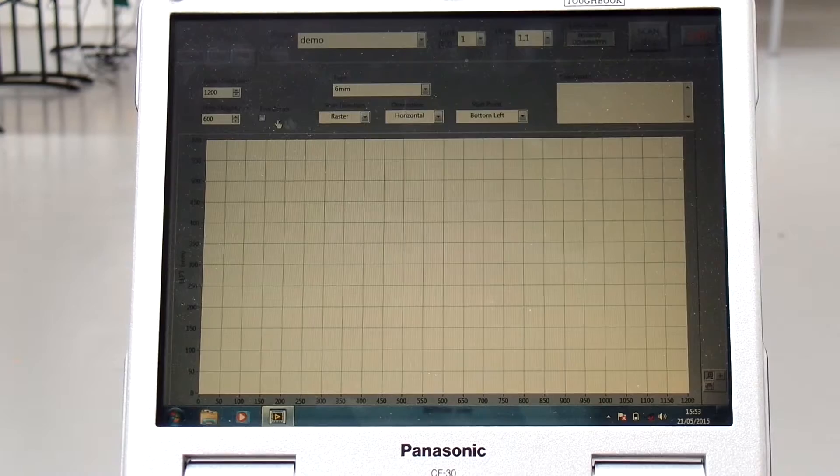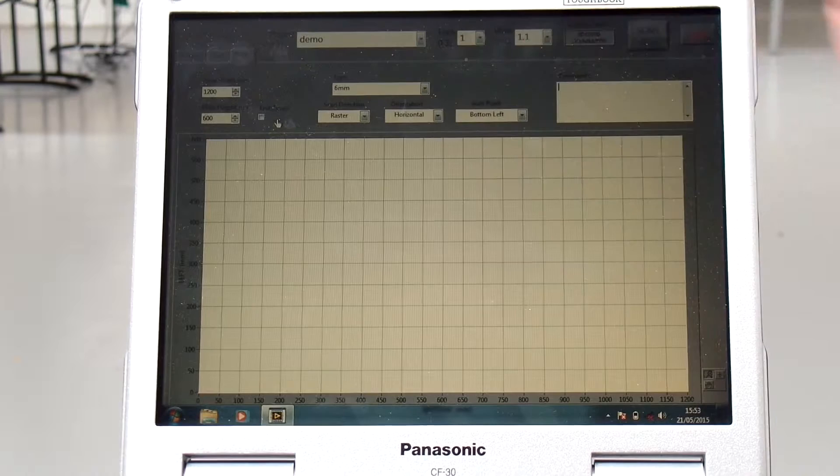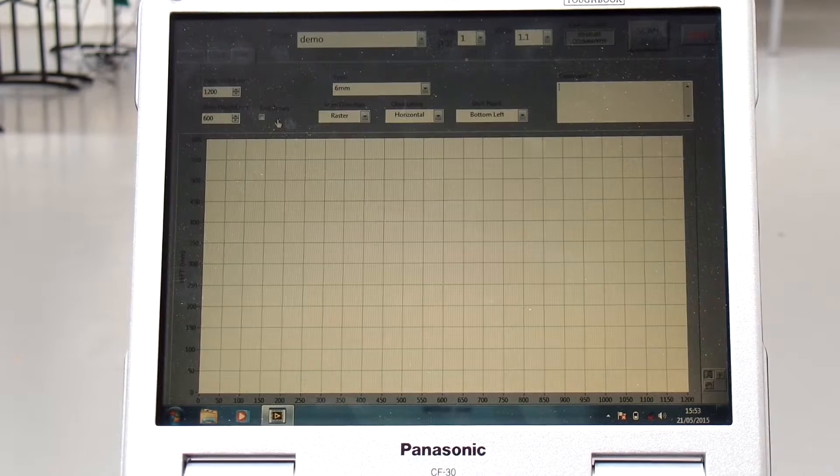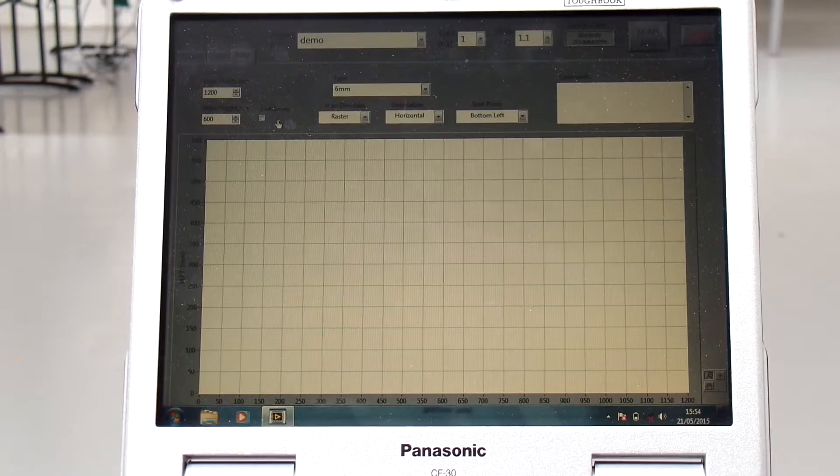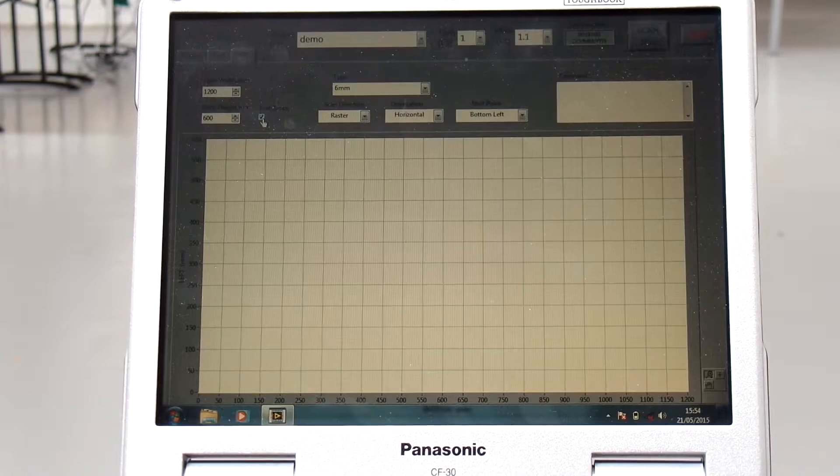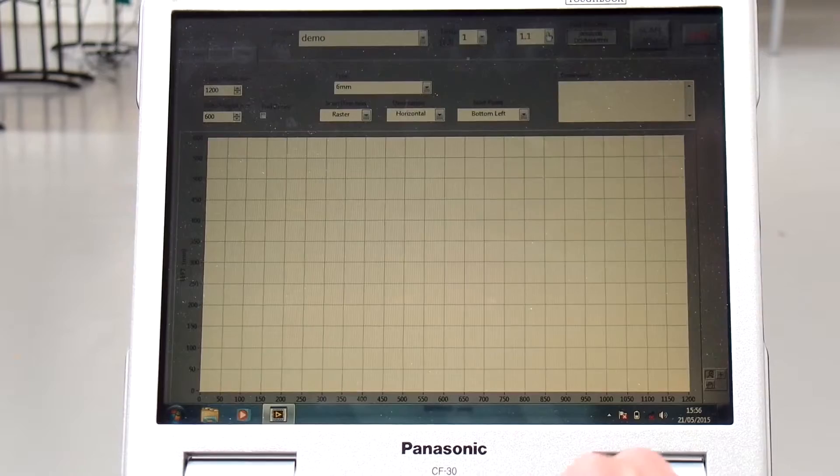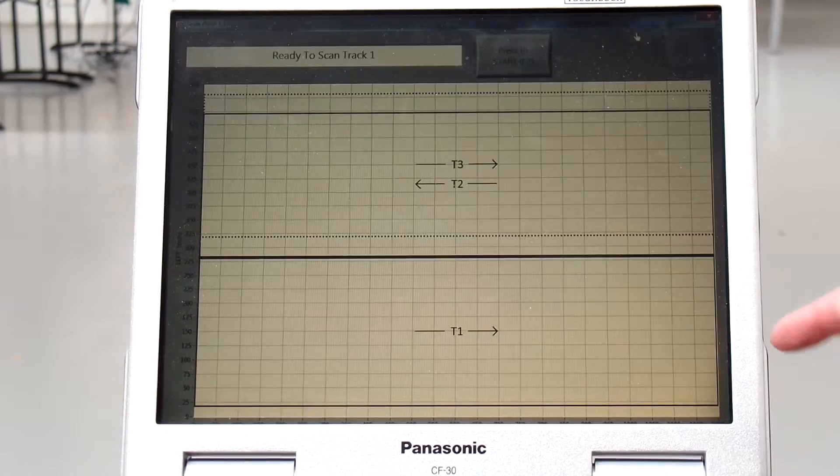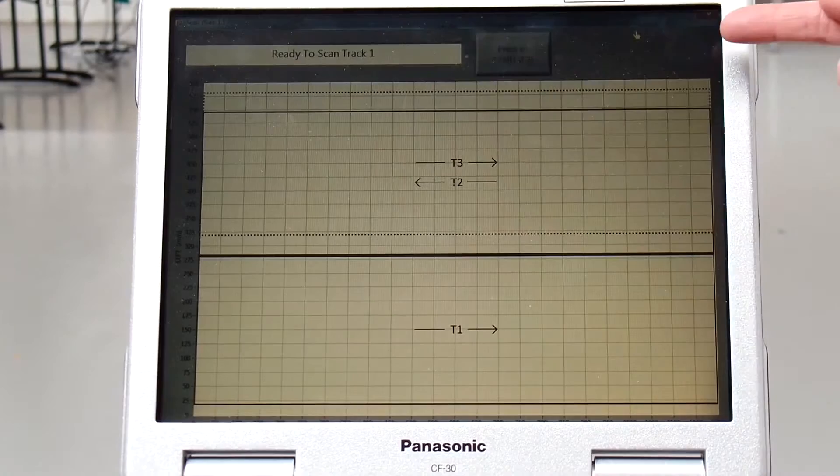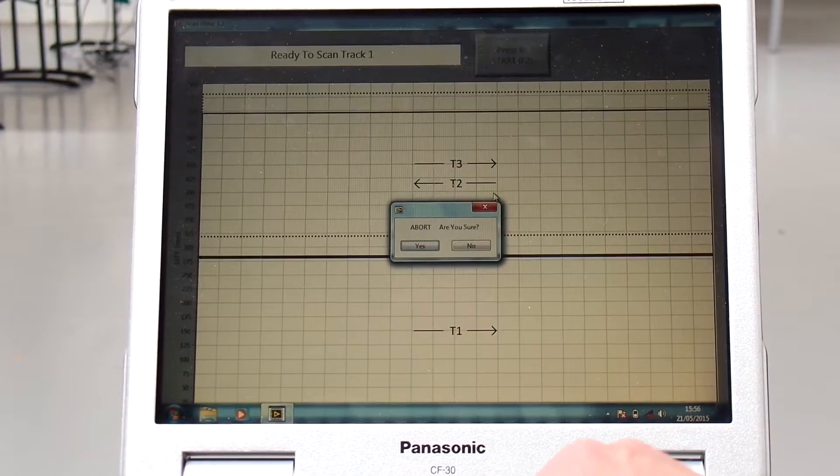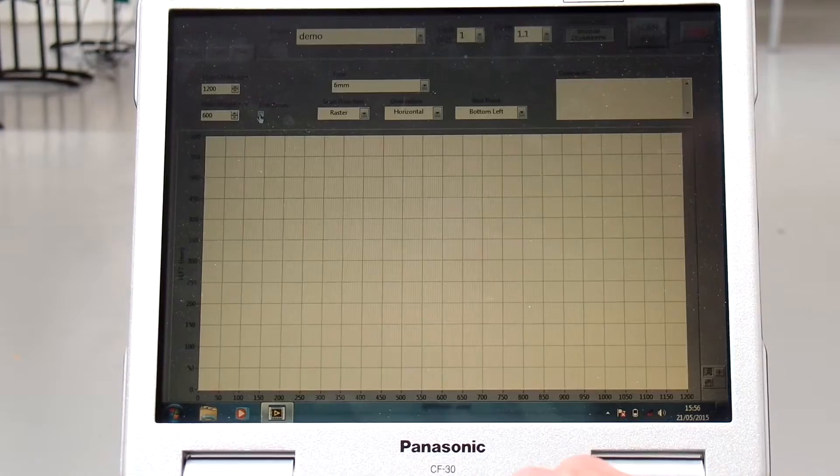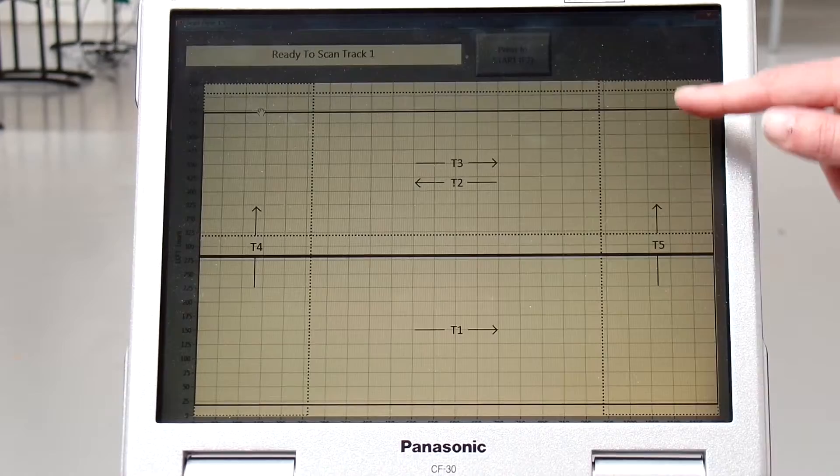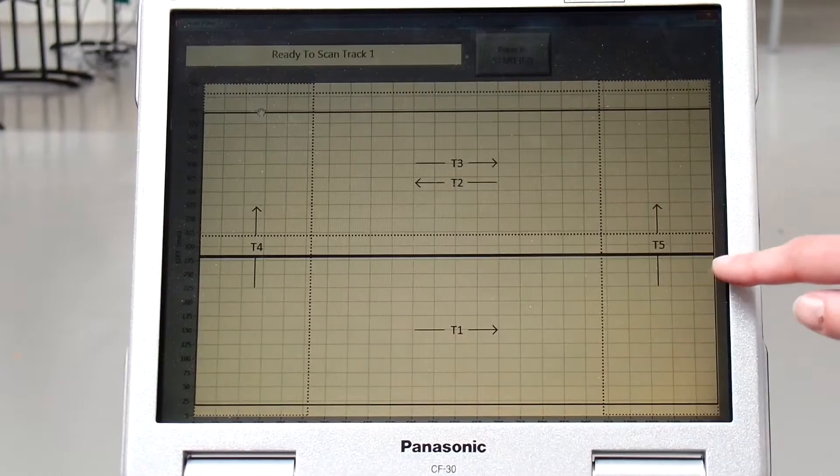End zones is a useful feature of the software. Because the scan head has an active sensor in the center of the mechanical assembly, it is not possible to get that to the edge of a scan plate. Therefore, at the edges of the plate, there is normally an unscanned area. By clicking on end zones, this allows you to scan that area to fill in 100% of the plate. The next step is to press the scan button or press F5. This takes us to a screen where we can see the scan strategy: Track 1 in this direction, followed by Track 2 and Track 3 to complete the plate. If I select end zones and then press F5 to start the scan, you can now see that end zones are now incorporated in the scan strategy as Track 4 and Track 5.